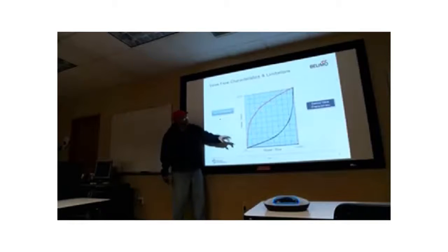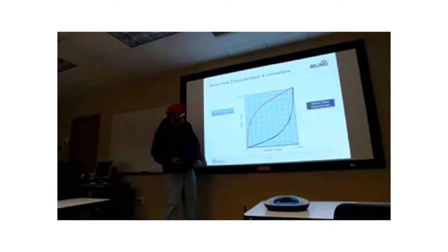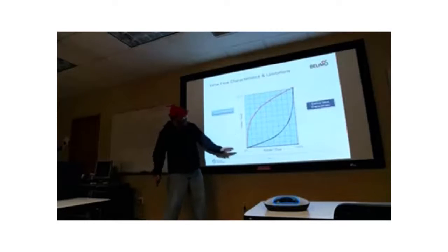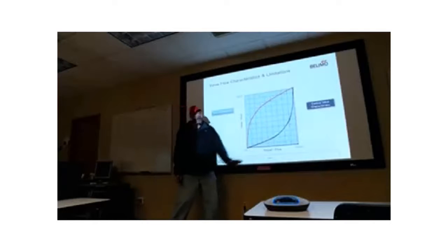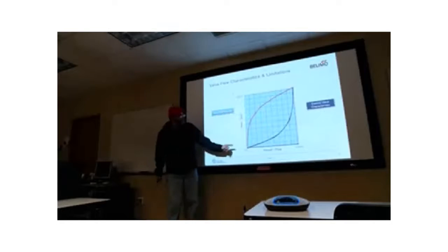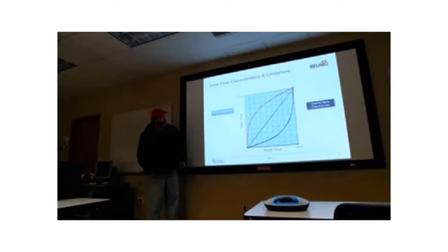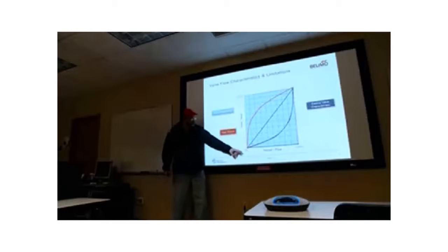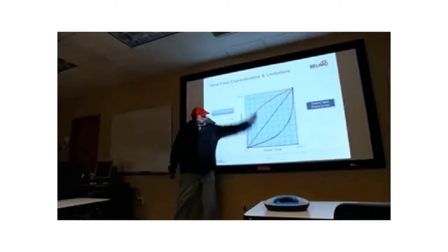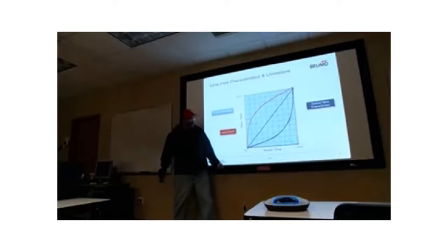That's what we're doing. So if you look at those two curves, and we do this on purpose because these are idealized curves, we call it the footfall, right? You've got the equal percentage curve on the bottom. You've got this coil characteristic curve on the top. And so here's the deal. From a control standpoint, here's what we want to do. We want to use the valve characteristic to offset the nonlinearity of the coil, and where the rubber meets the road is right here in the middle.